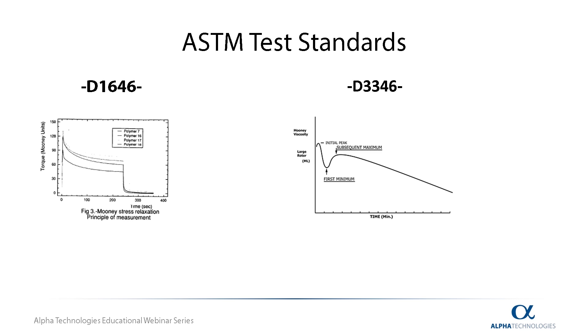This test is separated into three parts: the measurement of Mooney viscosity, stress relaxation, and pre-vulcanization characteristics. Each of the three measurements are recorded by a metal disc embedded in a rubber specimen contained in a rigid cylinder maintained at specific pressure and temperature. For viscosity, the rotor is rotated during the test at a constant rotational speed.